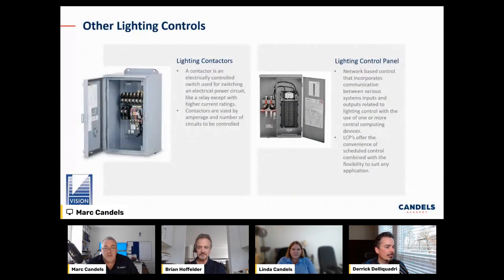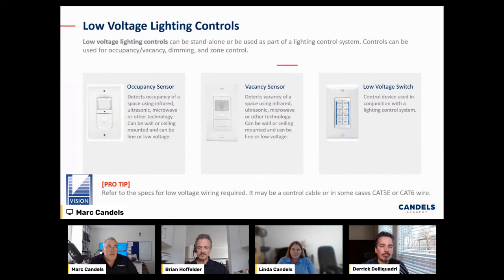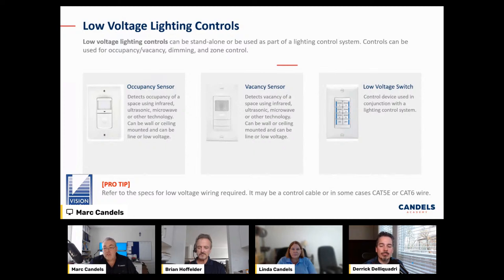Other lighting controls include lighting contactors and lighting control panels, then we get into the low voltage stuff, which is the meat and potatoes we want to talk about today. You'll have line voltage or low voltage occupancy sensors. Read the specs and drawings to know which type you have. A key tip: if it's a small closet, you can get by with a line voltage 120 or 277 volt occupancy sensor. But if it's a large open area, you'll need multiple power packs, so the sensors will likely be low voltage controlling those power packs.